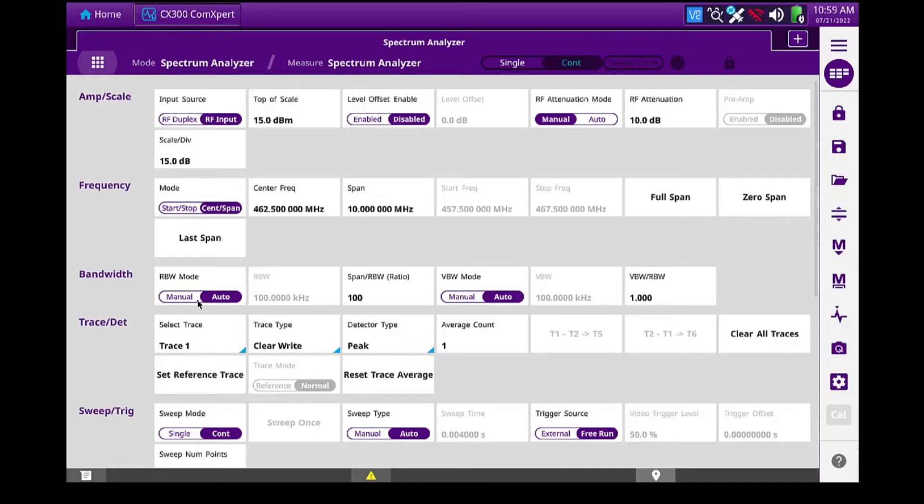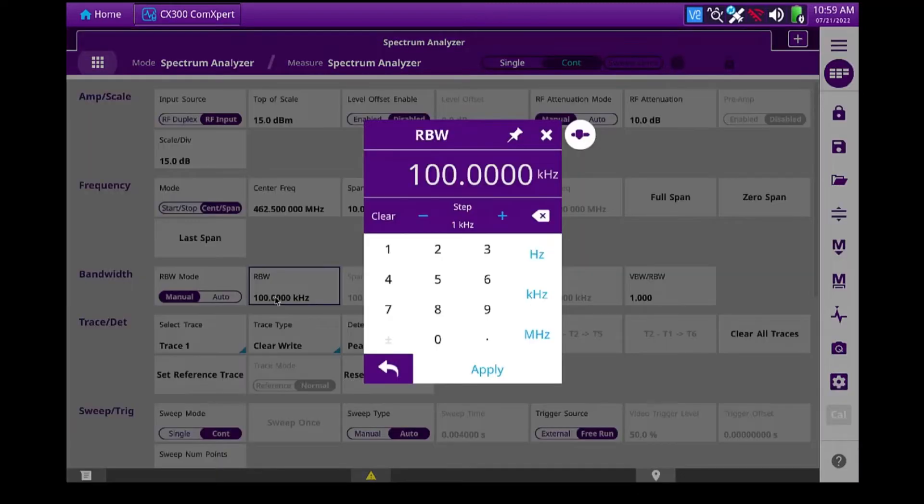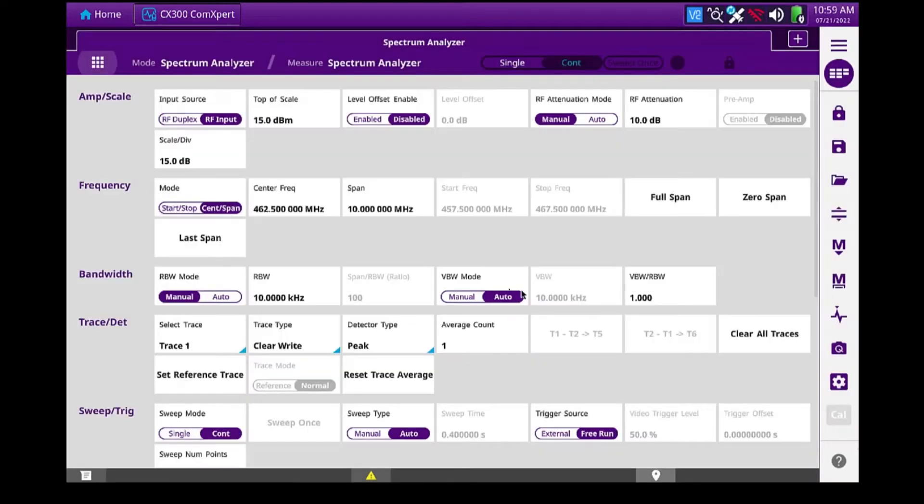And then we'll go down to bandwidth. I'm going to set this to manual mode also. And I'm going to change the resolution bandwidth to 10 kilohertz. This will give me a little bit lower noise floor.